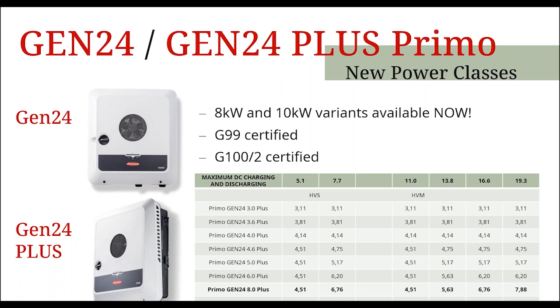Another question, will that be able to start induction loads in off-grid? They don't have transformers inside, so are they able to start loads like compressors or motors? Yes, depending upon what the initial startup current is. As I mentioned, with the 3.6 kilowatt unit, we can go up to 4.6 kilowatts of power on startup, or for a short 5-second period. Obviously, the larger the inverter, the more suitable it is for those larger loads. But if there are specific projects and specific loads, it's probably best if you send over the details and we can check those with the product management team and get some advice on specific issues there.